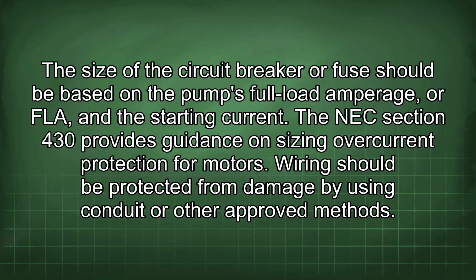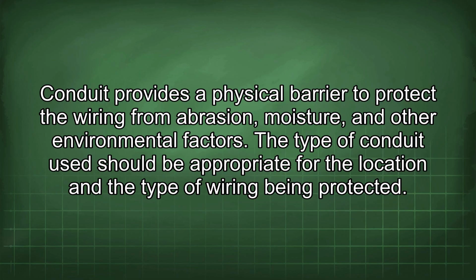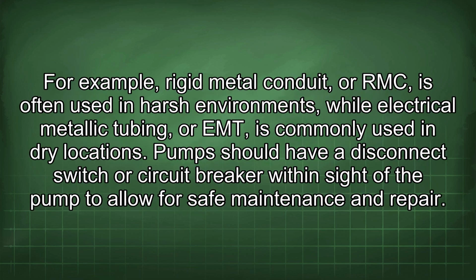Wiring should be protected from damage by using conduit or other approved methods. Conduit provides a physical barrier to protect the wiring from abrasion, moisture, and other environmental factors. The type of conduit used should be appropriate for the location and the type of wiring being protected. For example, rigid metal conduit, or RMC, is often used in harsh environments, while electrical metallic tubing, or EMT, is commonly used in dry locations.